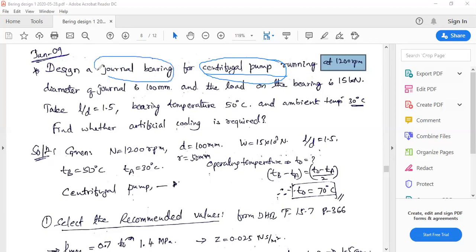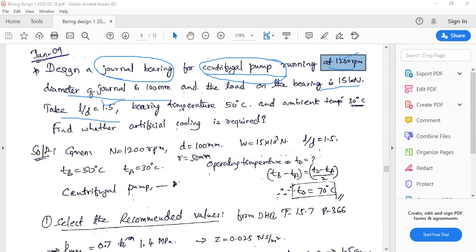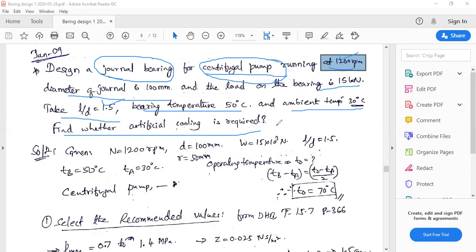The centrifugal pump is the specific application for which the journal bearing is to be used. The rotor is rotating at 1200 rpm and the journal is 100 mm diameter. The radial load on the bearing is 15 kilo-newtons. The L/D ratio is 1.5, bearing temperature is 50°C, and ambient temperature is 30°C. We need to find whether artificial cooling is required - this is a question of thermal equilibrium.